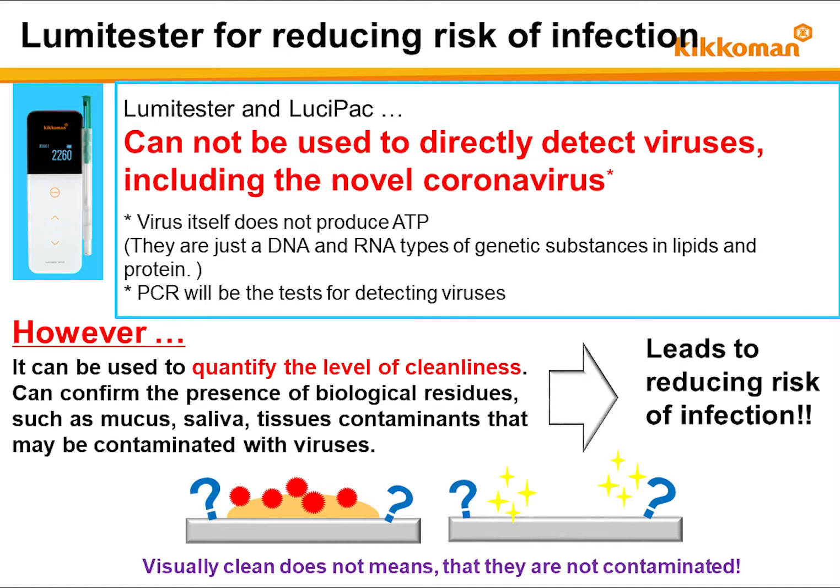Now I would like to explain how to use the Lumitester and LuciPac. It is important to mention that the ATP test or A3 test performed with the Lumitester and LuciPac cannot directly detect viruses, including COVID-19. This is because viruses do not produce or contain ATP, ADP, and AMP. In order to measure viruses directly, PCR or antigen antibody reaction tests are required.